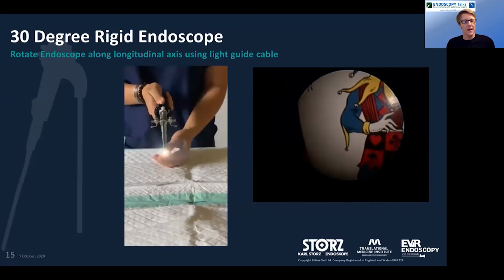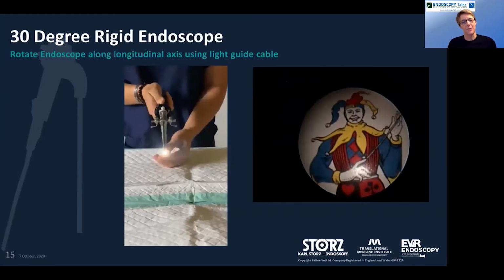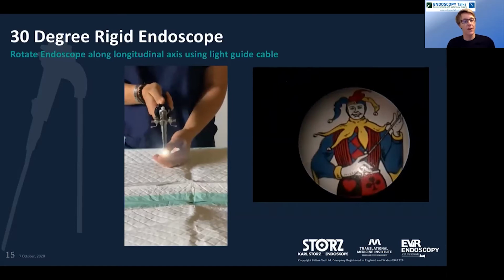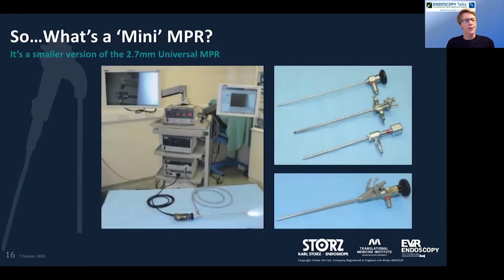And this is absolutely vital in feline endoscopy because everything is so miniaturized and a lot more tricky compared to medium-sized dogs. So this is why we opt for a smaller diameter and opt for a 30-degree oblique. So the MPR typically, if you see that in literature, that's typically referring to the 2.7 millimeter 30-degree oblique. When you see mini MPR, that's just a miniaturized version of a multipurpose rigid endoscope. So a mini MPR is a 1.9 30-degree oblique.